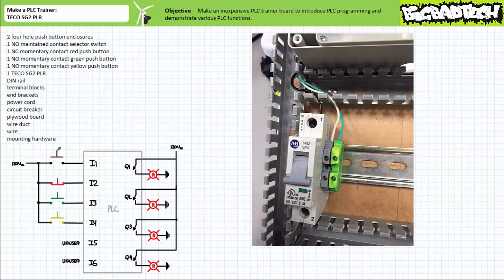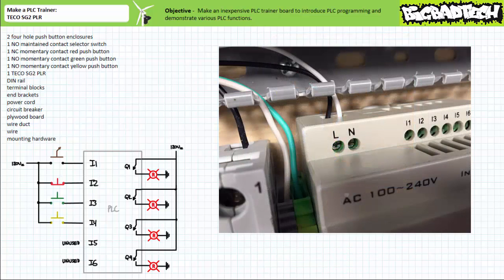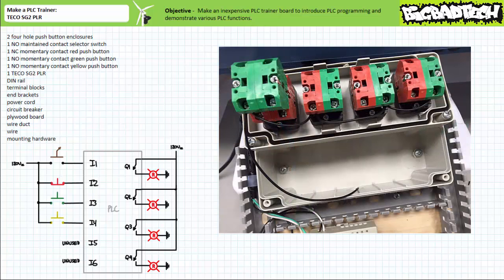Surround the din rail and push button enclosures with wire duct, forming kind of like an H with two horizontal rungs. Mount the cord and secure the board with a strain relief, then land the line, neutral, and ground wire respectively on the circuit breaker, terminal block, and grounding block. Now mount the TECO SG2 PLR next door, then route the line output of the circuit breaker and neutral terminal block to the line and neutral input of the TECO SG2 PLR. Next, we need to wire up our inputs. Start by wiring the line output of the circuit breaker to the input of each switch. The black wire serves this purpose. Note the daisy chain connection pools the input terminals of the normally open maintained contact selector switch, the normally closed momentary contact red push button, the normally open momentary contact green push button, and the normally open momentary contact yellow push button.